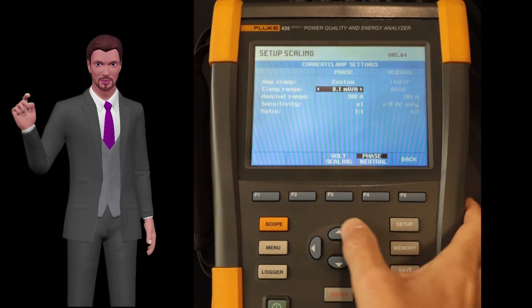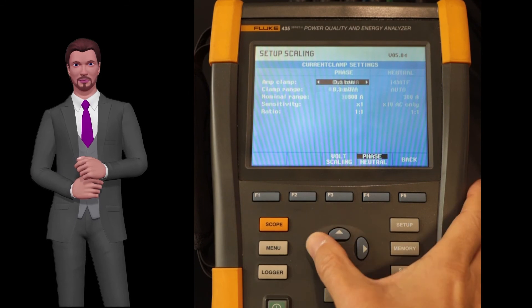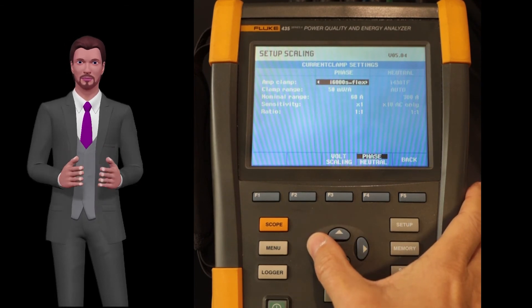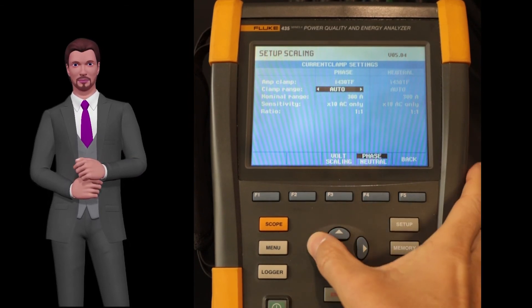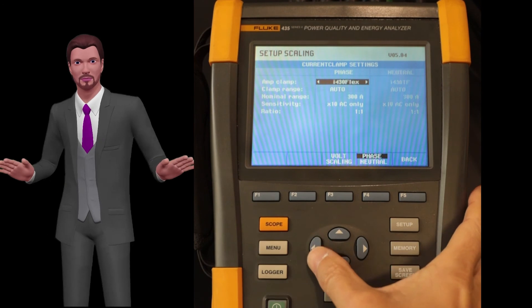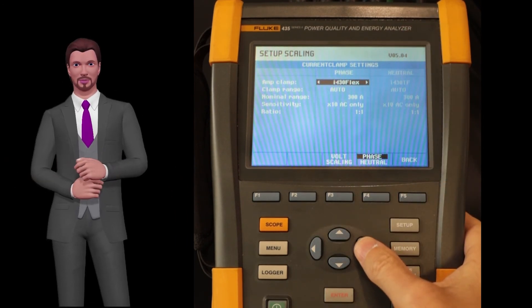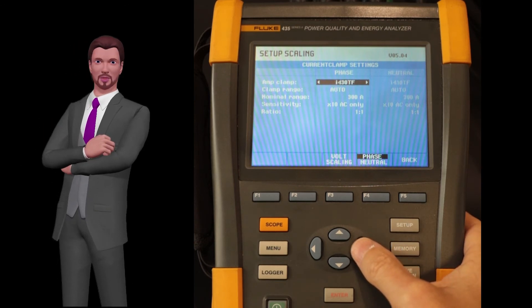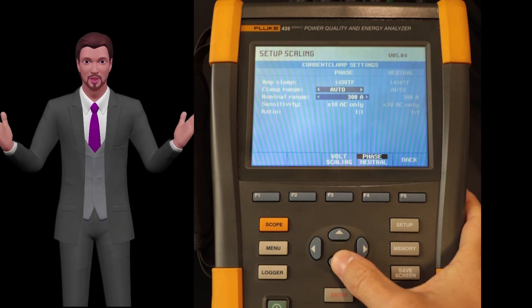In my case, I select the I-430 TF probe and since it is a flexible probe self powered by the unit itself, in the clamp range option auto appears, a parameter that in this case we cannot change. You can also see a probe called I-430 flex, but this probe was the probe included with the obsolete 435 series 1, so it should not be selected. Once the probe is properly selected, as I say in my case the I-430 TF, we go down to the parameter called nominal range.